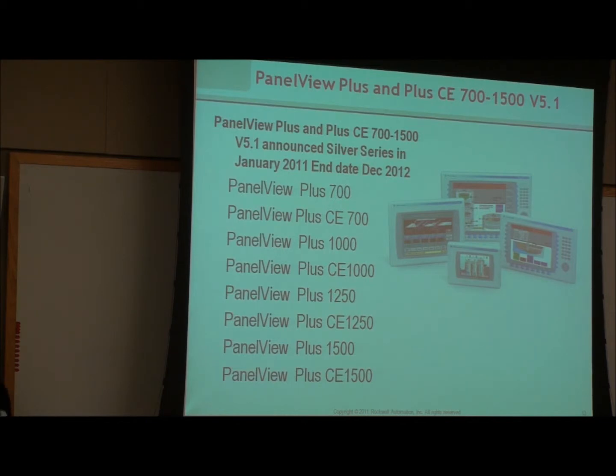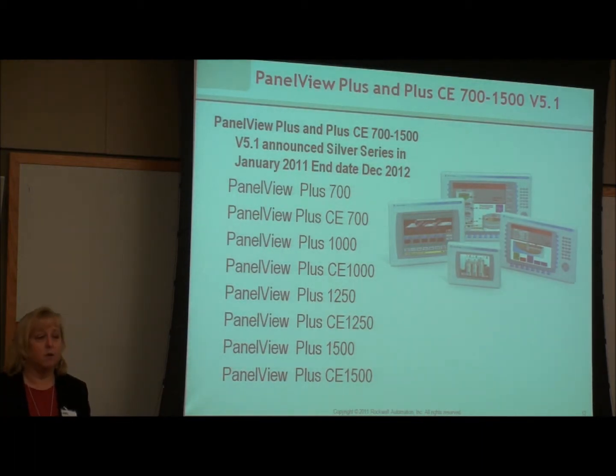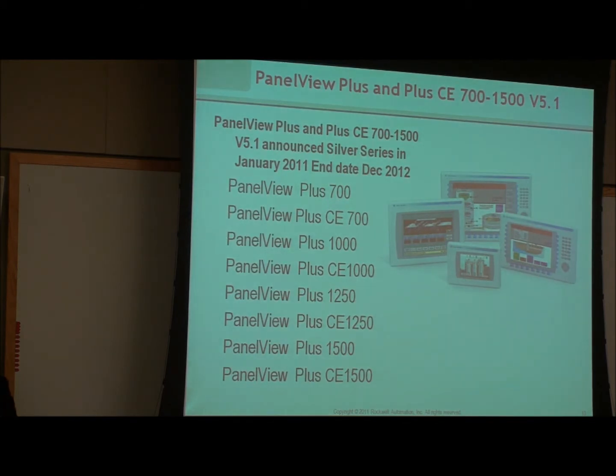PanelView Plus and PanelView Plus CE, sizes 700 to 1500, went into silver series in January 2011 at the same time as the Standard — that's version 5.1. We now have a new version 6.1. The reason it's put into silver series is that there was a hardware change in the PanelView Plus with version 6.0. What that means is you cannot take a PanelView Plus version 6.0 or 6.1 and flash it backwards — a 6.1 can go to 6.0, but you can't take 6.0 hardware and flash it back to 5.1, 5.0, or earlier. There's a distinct break point.